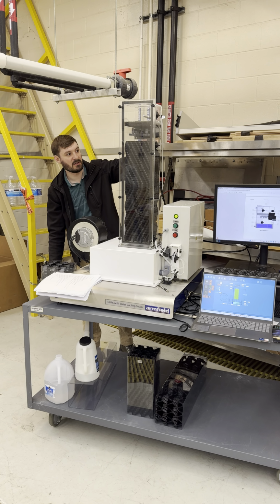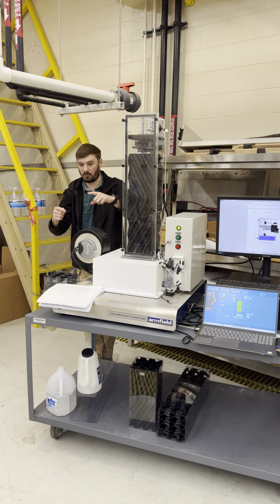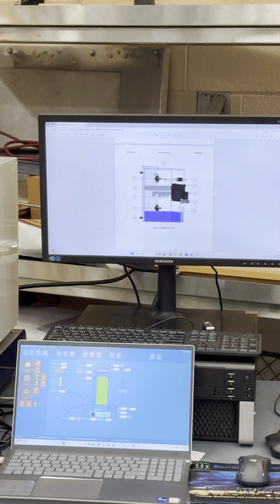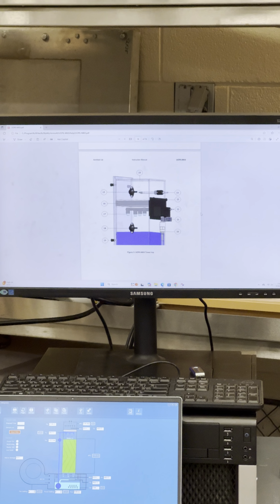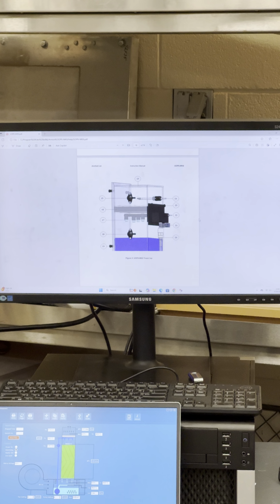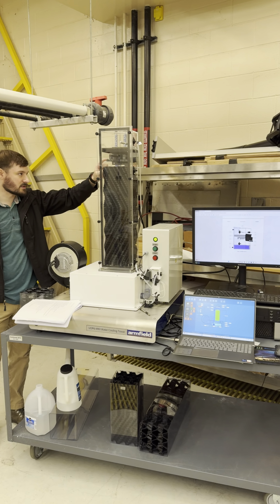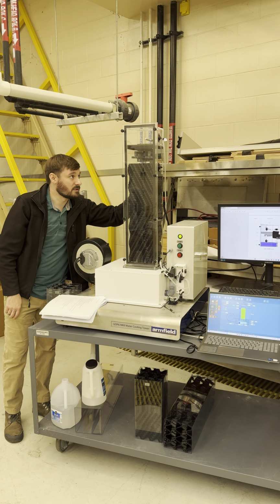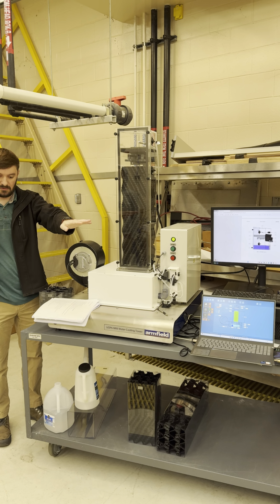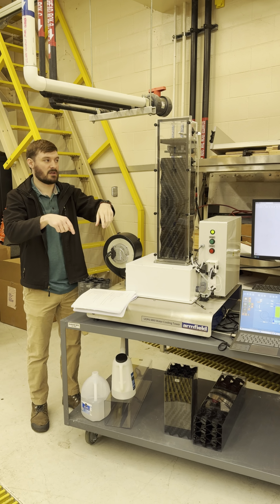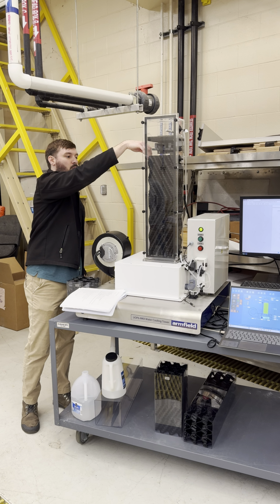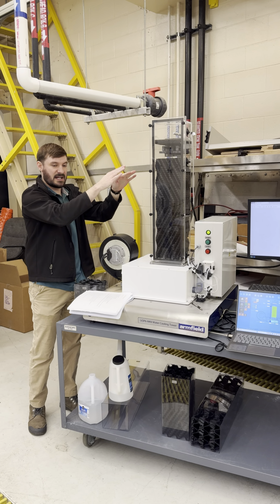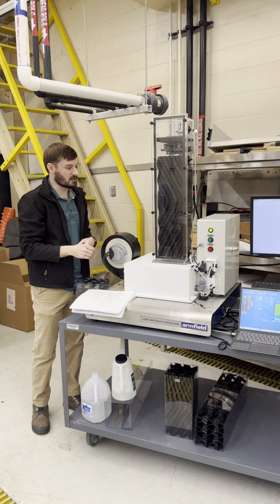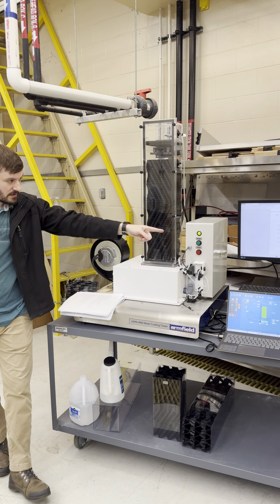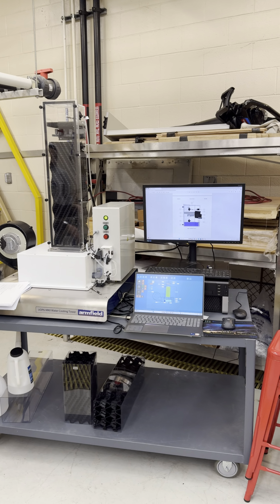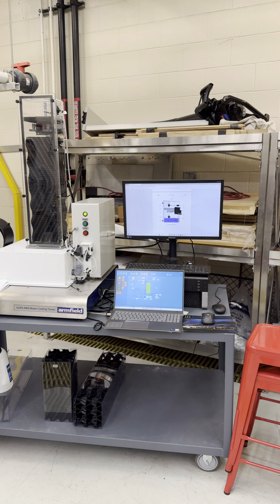There's a temperature probe up here, and also a flow meter right after where that tube connects into the inlet. And then there are the little spouts or nozzles. There are 20 of them. So there's 5 X's, 1, 2, 3, 4, and 5. Each one of them has 4 holes. And that evenly distributes the water over the top of the packing. Okay, it falls down, makes a film over the convoluted shape, and then falls out through the column to that diffuser back to the sump tank.